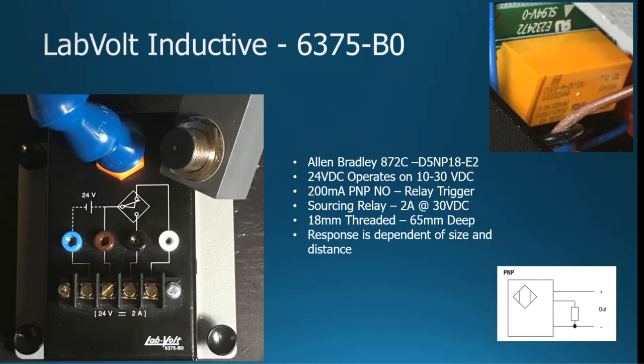As far as the actual sensor, it's an Allen-Bradley 872C D5NP18E2. So it's an inductive sensor that operates between 10 and 30 volts DC. It will be operating at 24 volts DC as our control voltage.